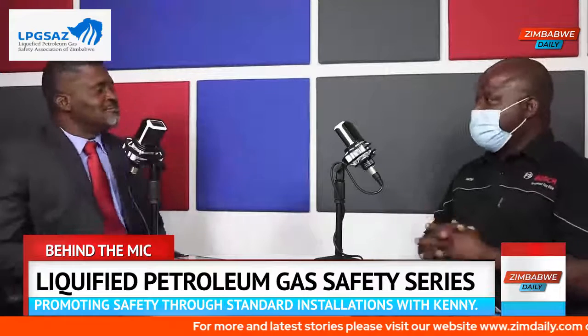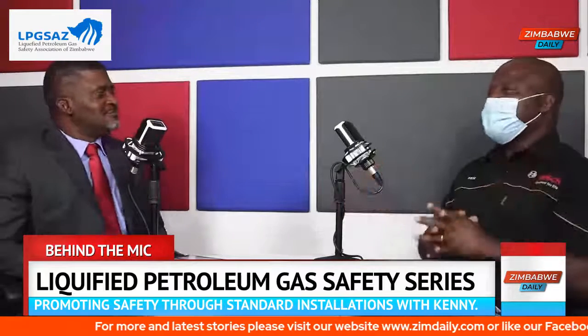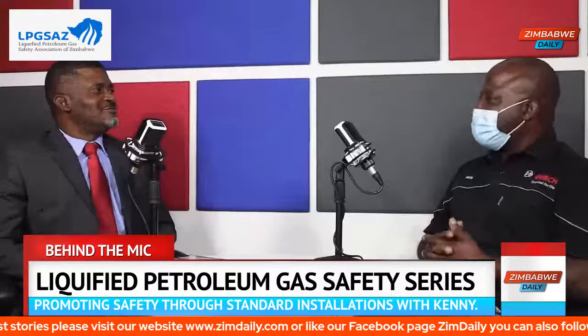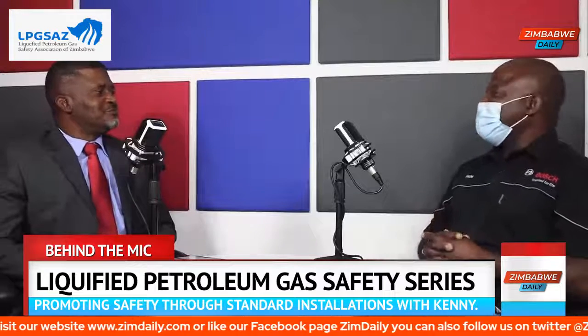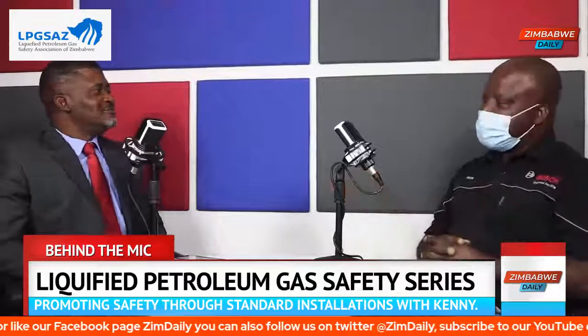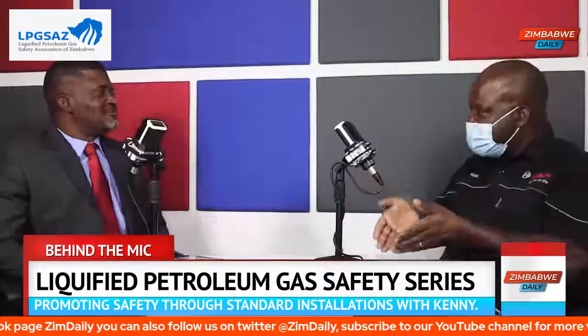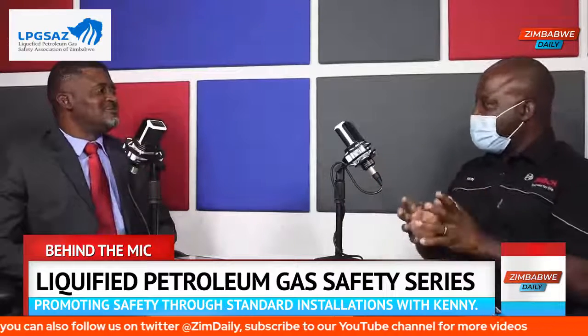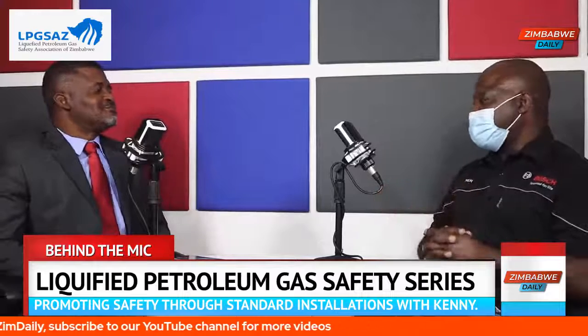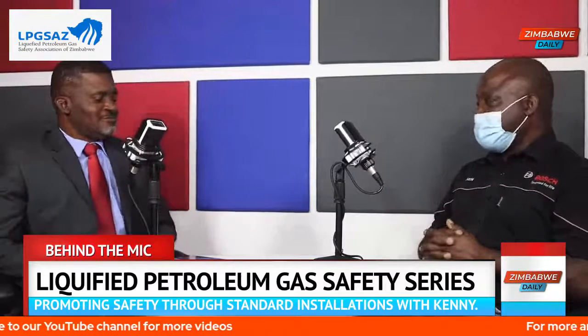Bylaws like simple ones that you must put your bottles not less than 1 meter away from the window, not less than 1 meter away from the door, not less than 2 meters away from an open drain. As I alluded to, gas is heavier. If it gets into the drainage system, and if there's a match or a light at some point, there's going to be a big explosion. Be wary of these things.